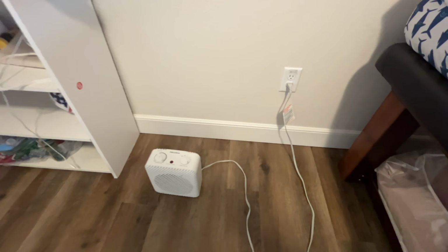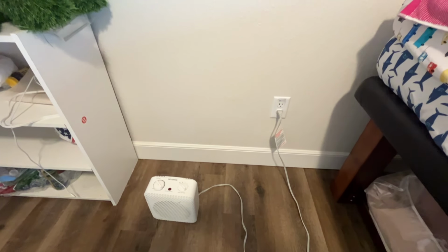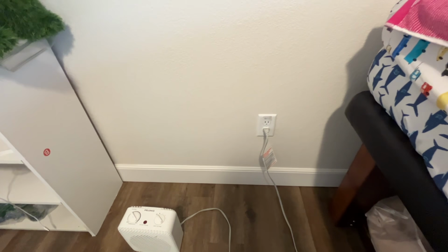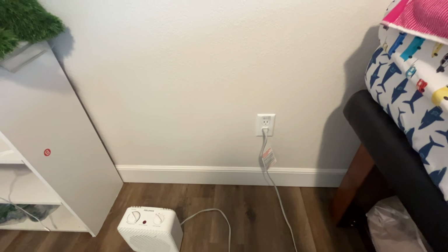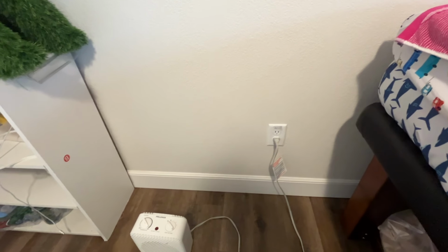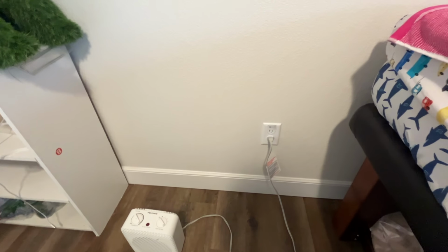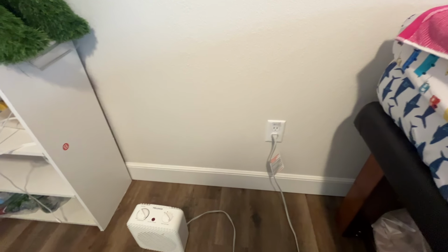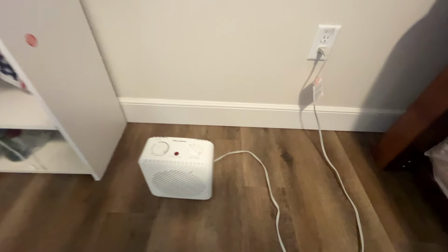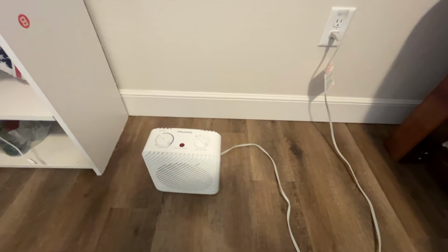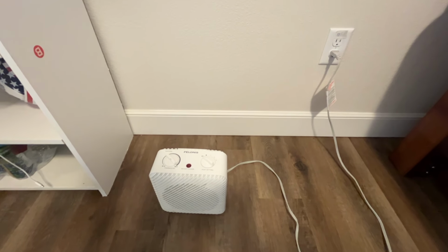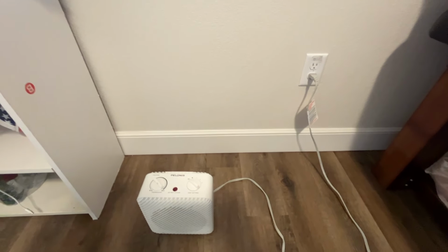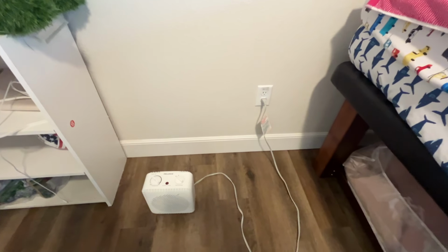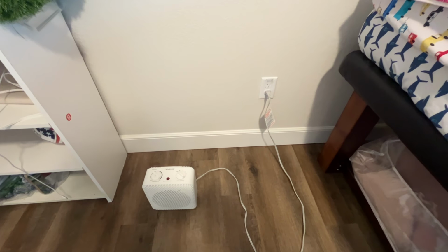But that's all it takes: run a load, check the voltage at each receptacle, and the one with the highest voltage is the first receptacle in the chain. If all you're looking for is that first receptacle, it doesn't matter if the load is on the last one or not, as long as it's not on the first one.